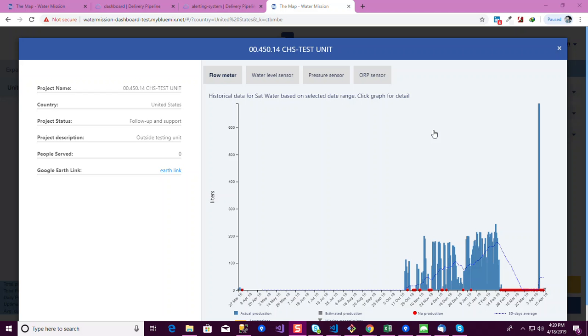And if we have another 4-20 milliamp sensor on port 3, then we use the low calibration and high calibration values of that sensor in the calculations of the other 4-20 milliamp sensor chart on port 3. And the remaining chart is the min-max chart: if the other 4-20 milliamp sensor is installed on port 1, then we use the ORP at position 1 as the minimum value and the ORP at position 2 as the maximum value, and plot the min-max chart on the map side.